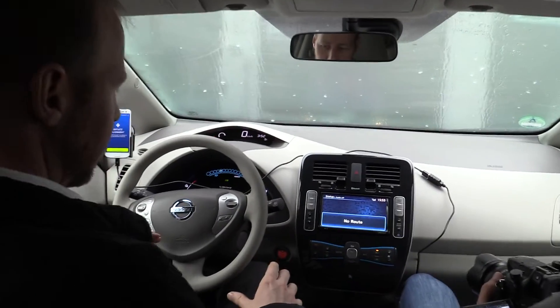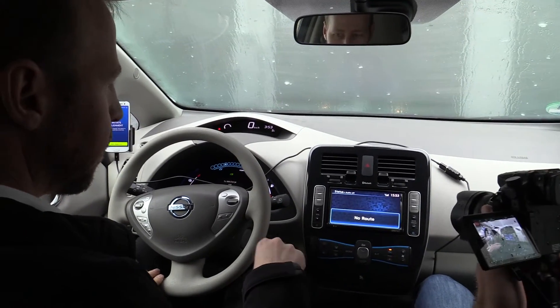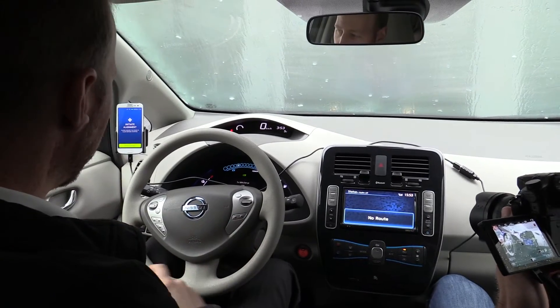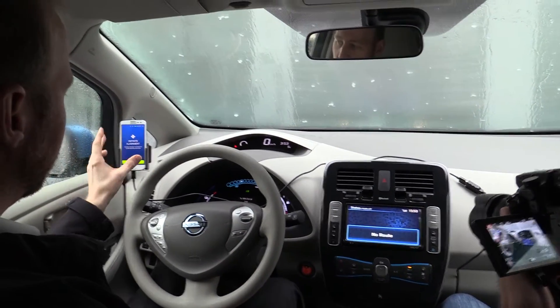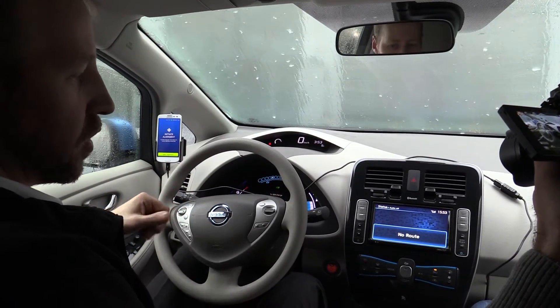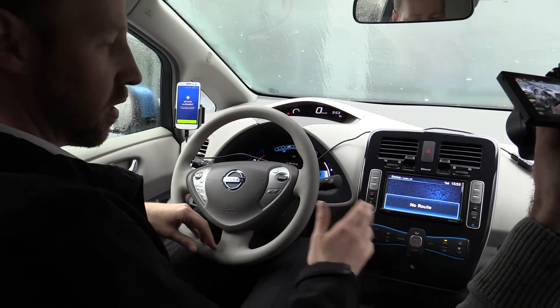What we've got here is a 7.4 kilowatt system installed in the Nissan LEAF. It's integrated into the high voltage network of the car including the charging system, and we use the cell phone here to give the information about the charging system and alignment to the driver. On a proper fully integrated system, that would obviously end up in the car's display.